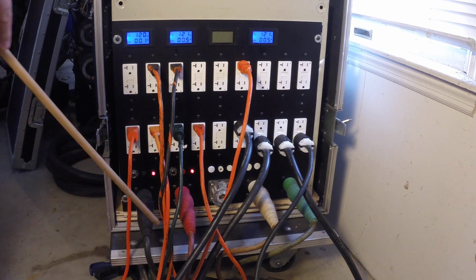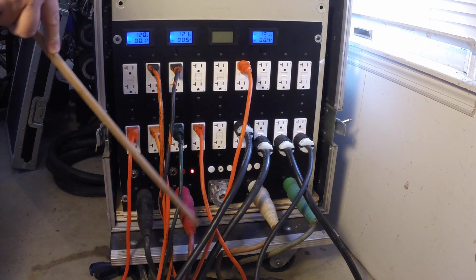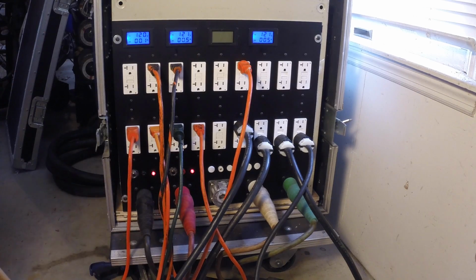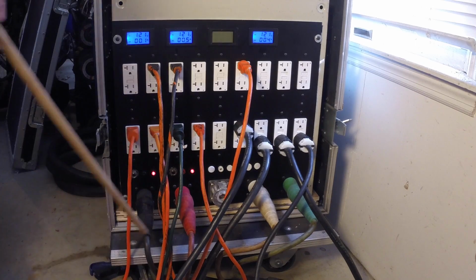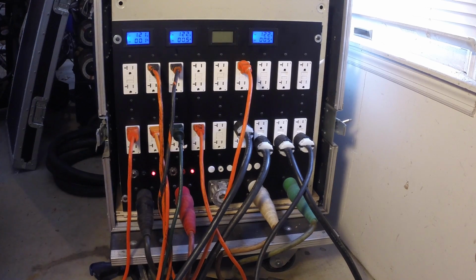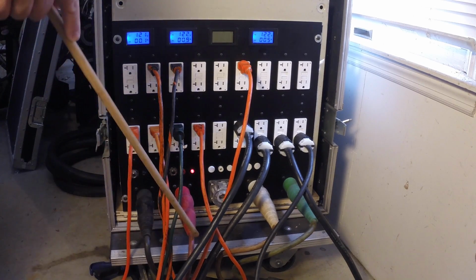But some other things with this panel, it's fed here with these cam locks. These are rated at 400 amps. I'm only drawing, maxing out at 100 amps per connector, so this is a 200 amp panel. We have two hots, a neutral, and a ground.